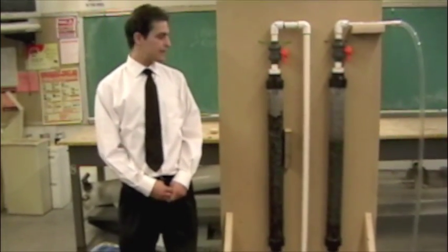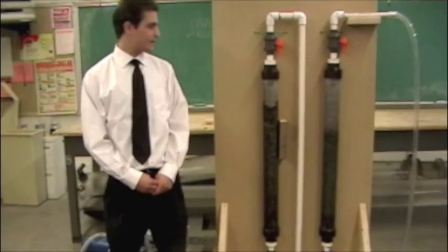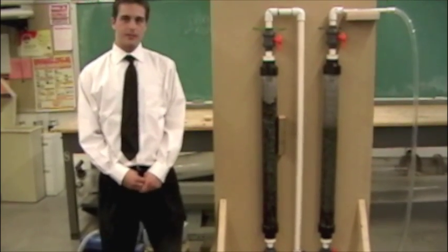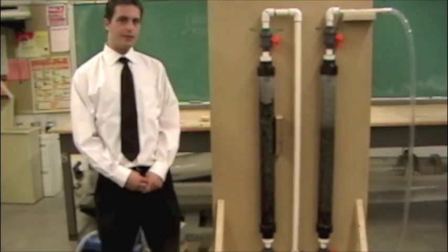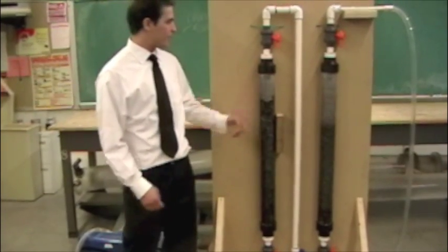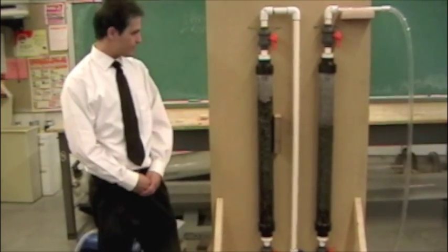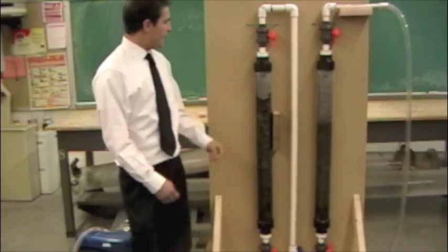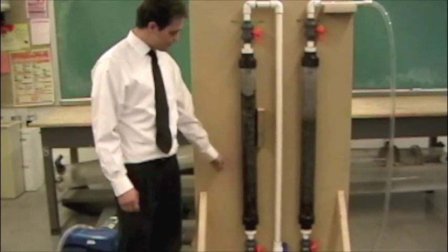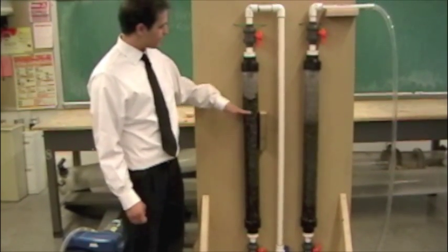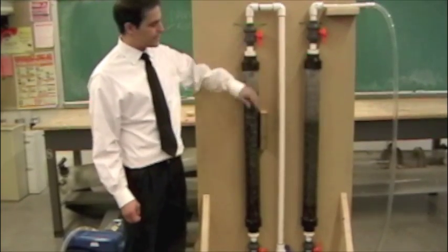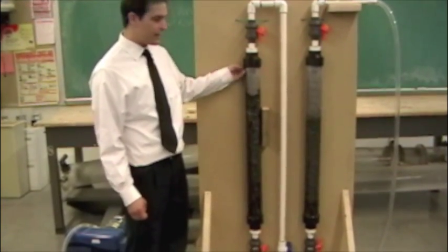Downflow is often used as a filter as well as treatment. We don't have any suspended particles in our effluent, so we will just have an upflow, and it won't require any backwashing throughout the system because it will not clog the pores. Instead of having the water just fall through with gravity, we will slowly raise it at a controlled flow rate to have an even contact time, and we will evenly treat and evenly exhaust the carbon.